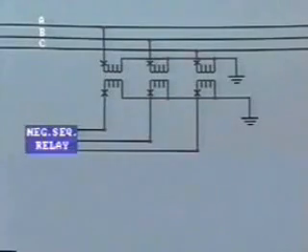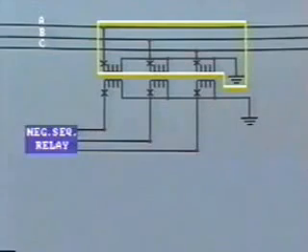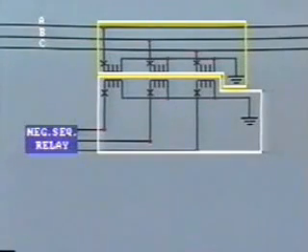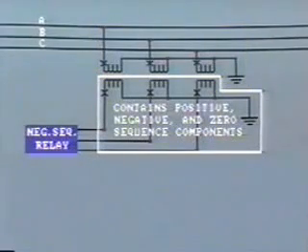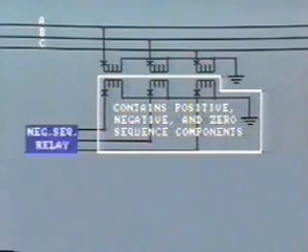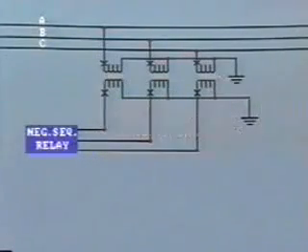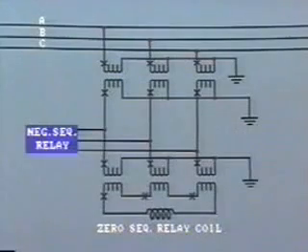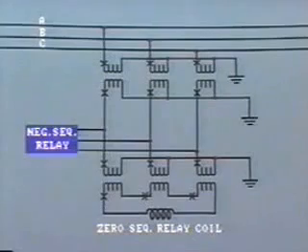Note that the zero sequence components, as they are all in phase, add together at this point and pass through the ground relay current coil. Now let's look at the VT connections. The primary and secondaries are Y-connected with grounded neutral. The secondary supplies potential containing positive, negative, and zero sequence components to the relay's negative sequence voltage coils. This enables the relay to detect the presence and magnitude of negative sequence voltages. Additionally, to detect zero sequence voltage, an auxiliary transformer can be connected like this.